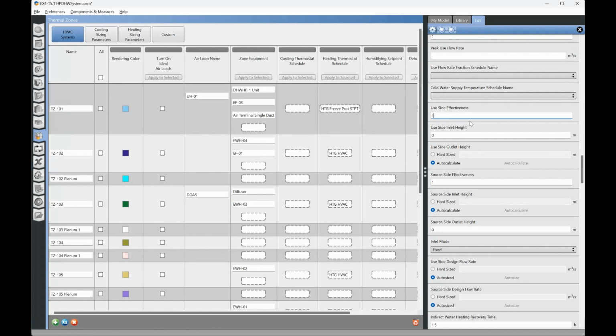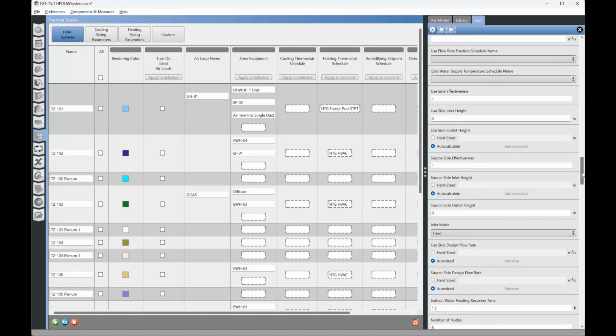Use side effectiveness. This is how effective the compressor is for transferring heat into the tank, and likewise for the tank transferring heat into your hot water loop. Since it's all just water and it's being mixed, you can assume that it's got 100% effectiveness. If you do have some sort of heat exchanger in between the compressor and the tank, or in between the tank and the system for safety purposes or something, this use side effectiveness would be something less than 1, because any heat exchanger you have in between those, you're going to lose that effectiveness.